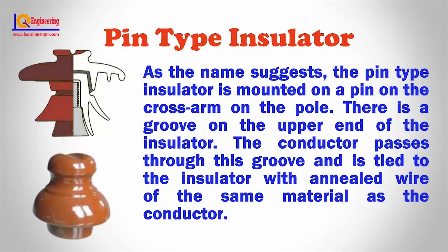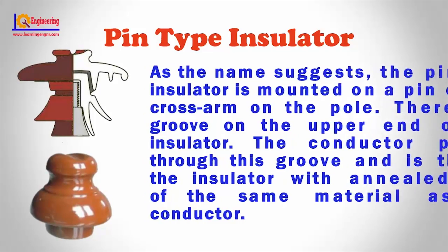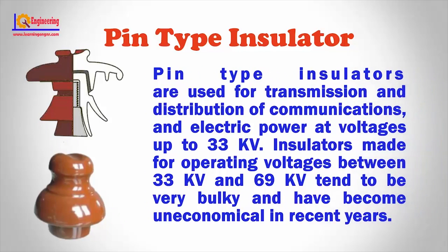Pin type insulator: As the name suggests, the pin type insulator is mounted on a pin on the cross arm on the pole. There is a groove on the upper end of the insulator. The conductor passes through this groove and is tied to the insulator with annealed wire of the same material as the conductor. Pin type insulators are used for transmission and distribution of electric power at voltages up to 33 kV.